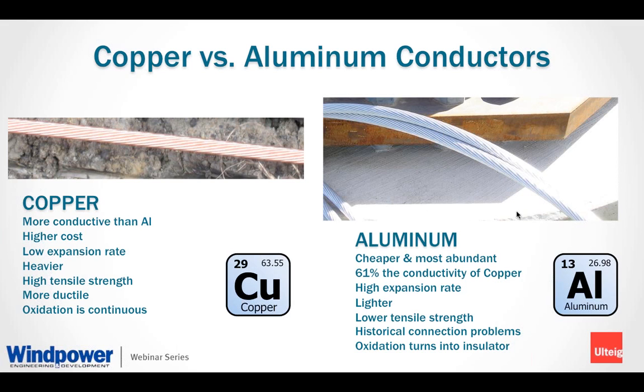Upsizing the minimum size aluminum conductor can sometimes offer a much cheaper method of energy loss reduction instead of reverting to copper. The benefit of having a larger diameter cable conductor is that the heat can be dissipated faster over a larger area. Kind of acts like a small radiator, if you will. While both metals have a corrosion issue in the environment, oxidation occurs on both copper and aluminum. The one thing about aluminum is the oxidation almost creates a thin layer of insulation around the metal. And that's why you never see aluminum used in grounding situations, because the grounds are directly exposed to the elements. That's why copper is always used in grounding situations.